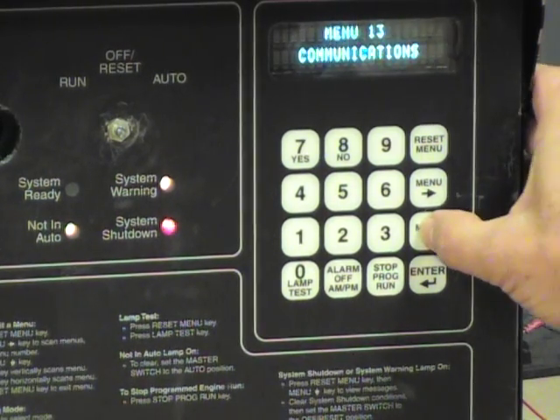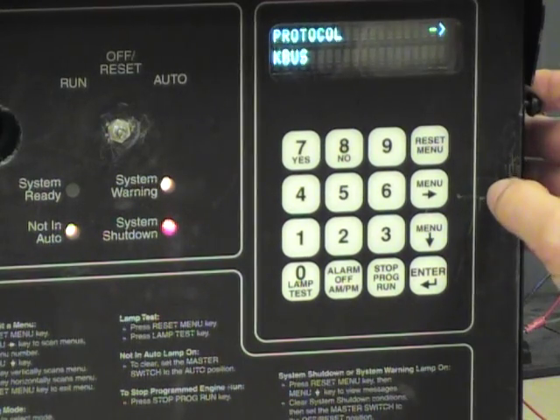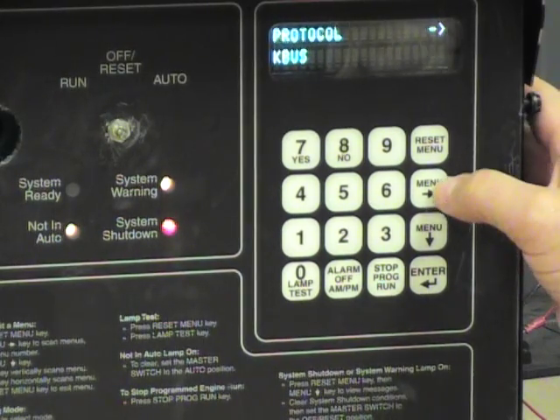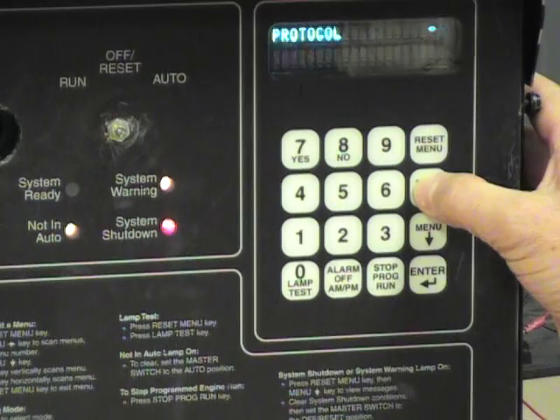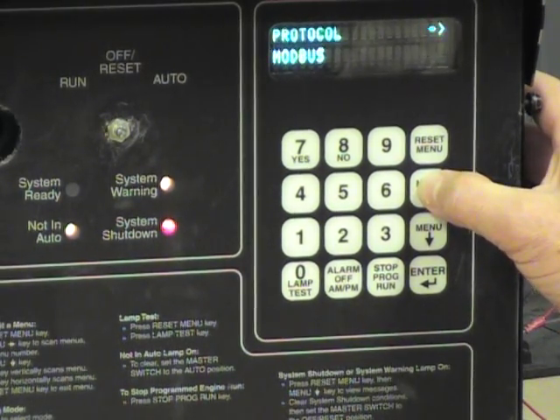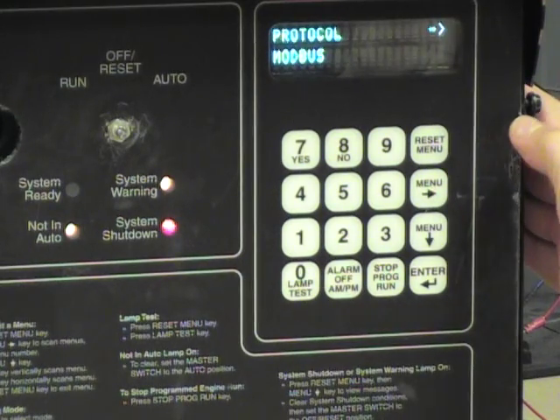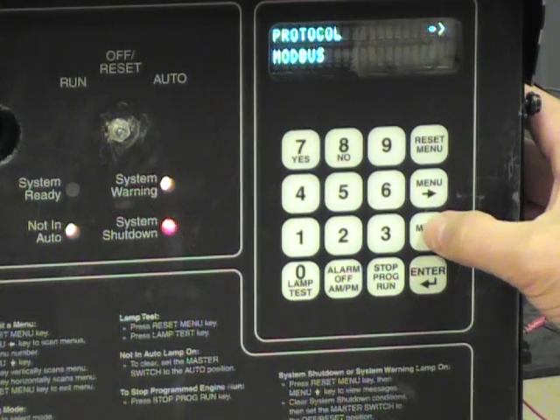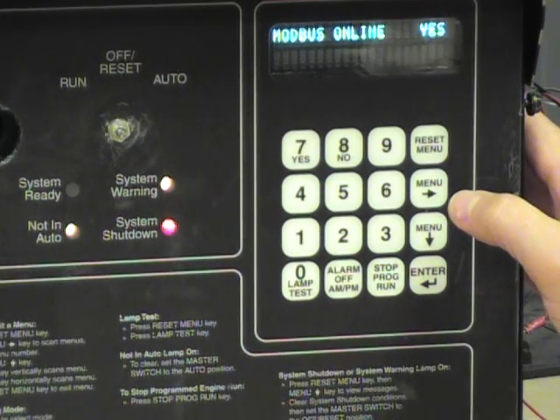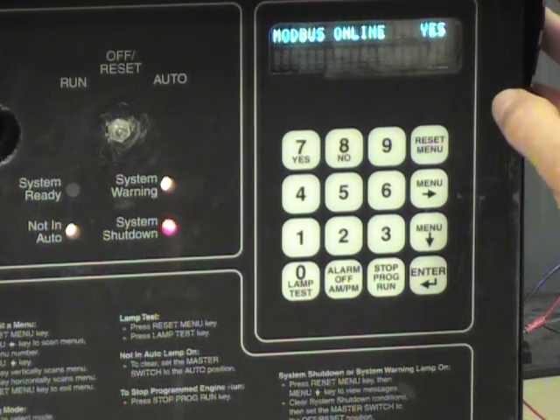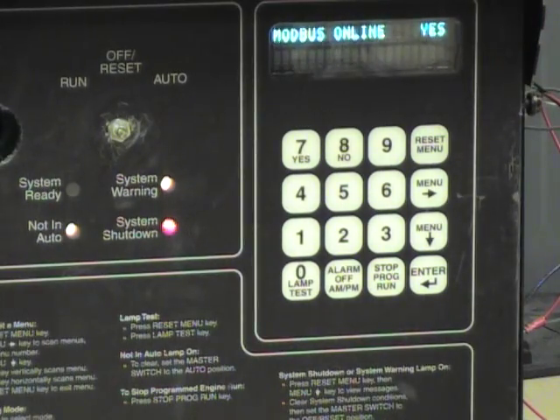I am going to push the down arrow key to begin. There are two protocols that the 550 uses: K-Bus and Modbus. I am going to use the right-hand arrow key to toggle between the two. We are not going to make any changes to the K-Bus configuration — we will go to Modbus. Then under Modbus I am going to press the down arrow key to take us down to the details. Modbus online should be set to yes. Should you find your unit saying no, press yes to change it.